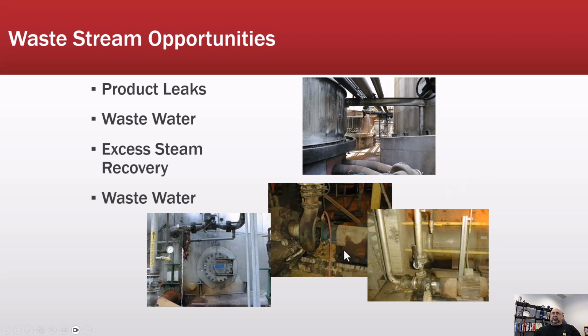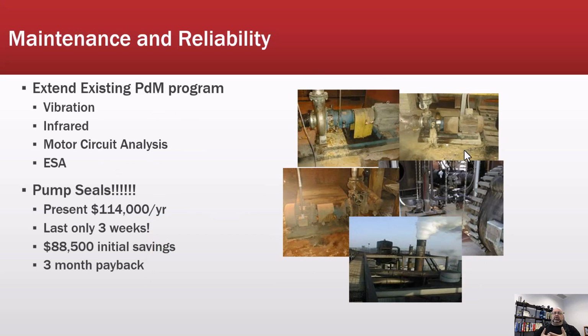Now, the problem is this all goes into their waste treatment plant, and that generates a lot of energy loss there because they have to return water cleaner than they take it in from the nearby river. So the maintenance and reliability aspect, they had a very not well-run vibration program. We recommended that being brought up to speed. An infrared program because they had loose connections all over the place, and nobody would. Well, and then of course, just like some other facilities I've gone into, the recommendation of shutting things down and then doing IR is kind of ridiculous, but people do that.